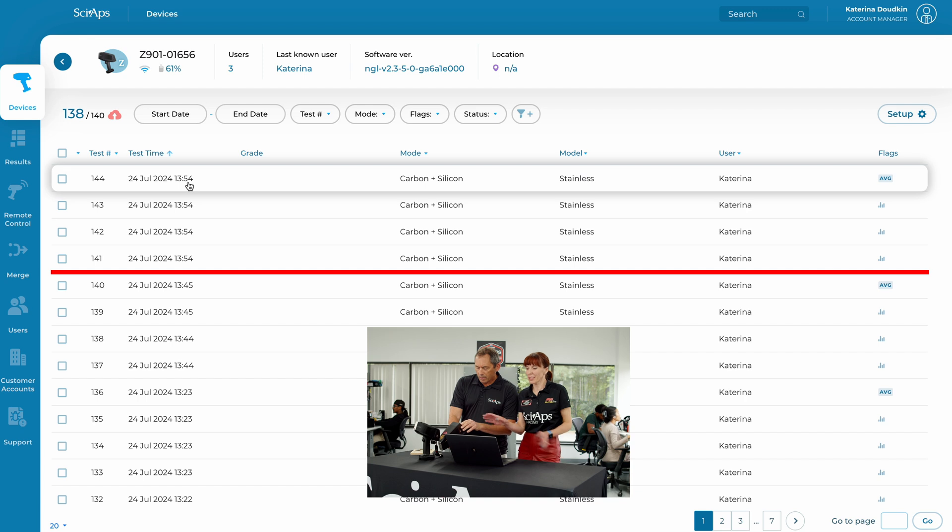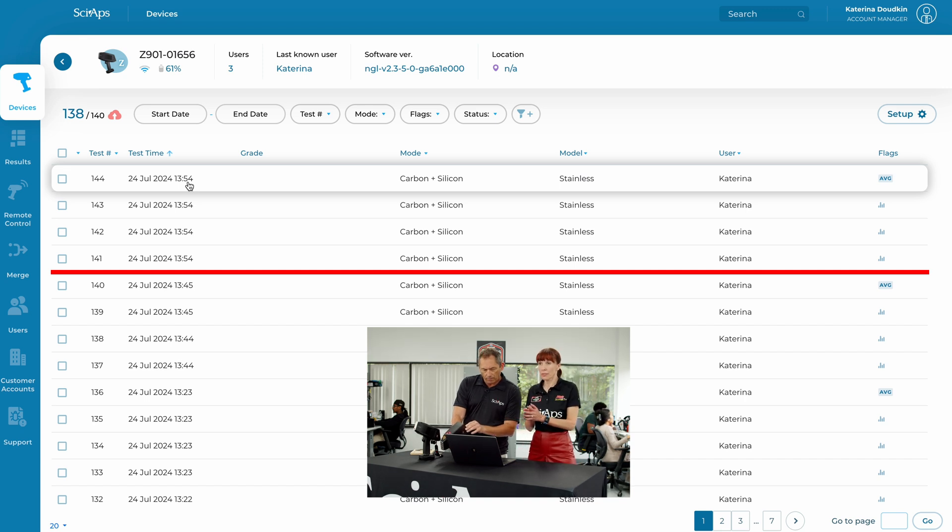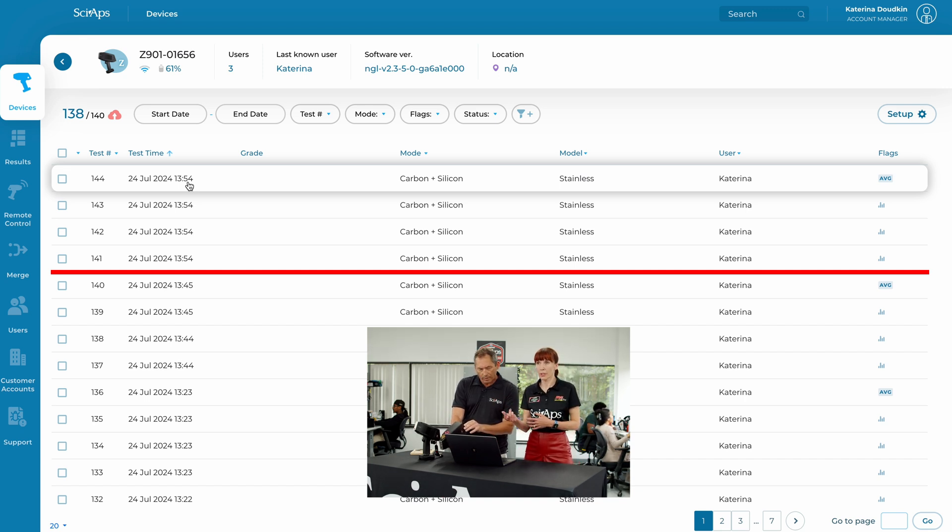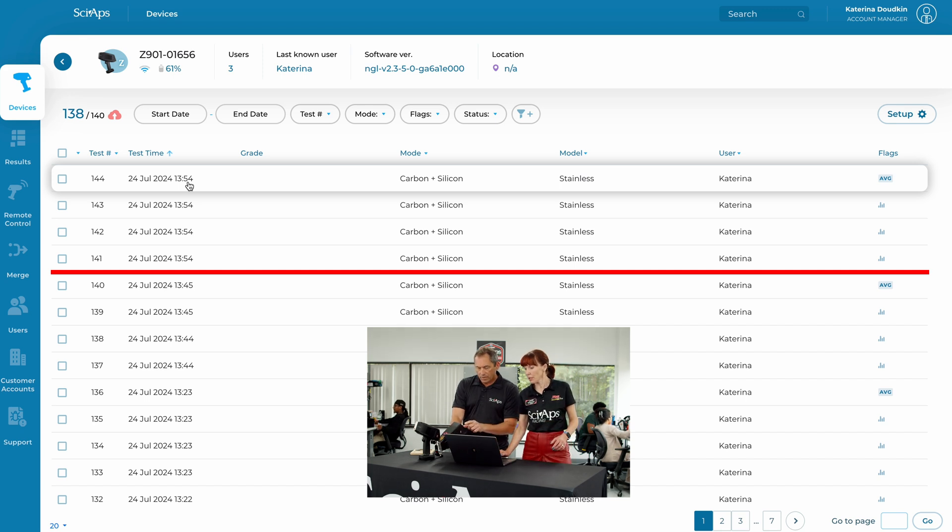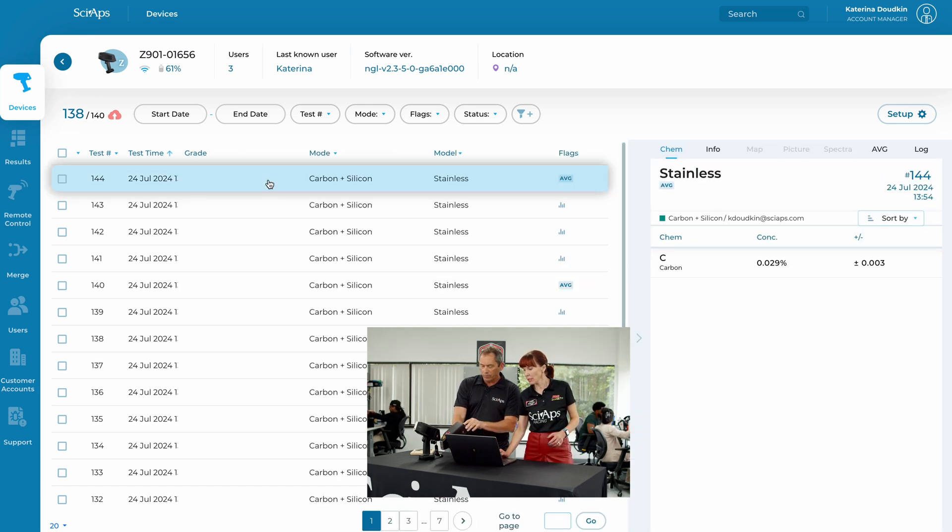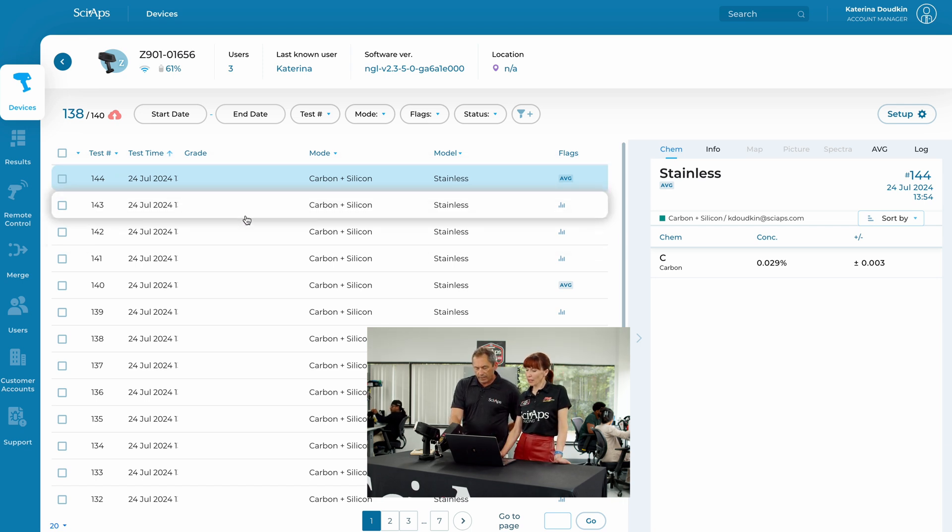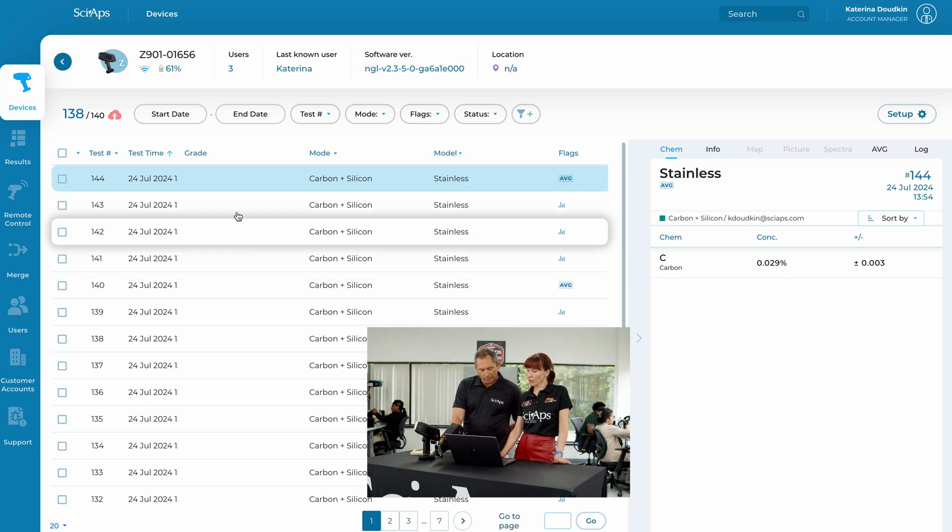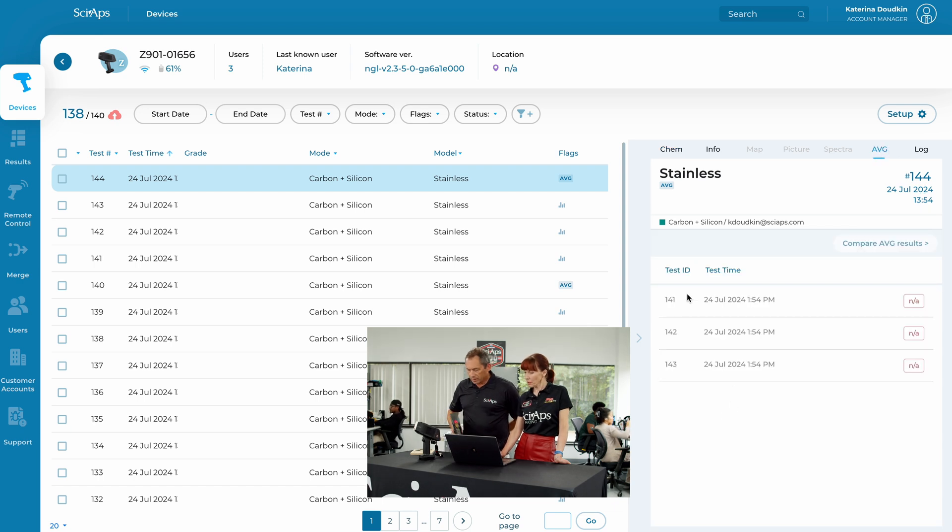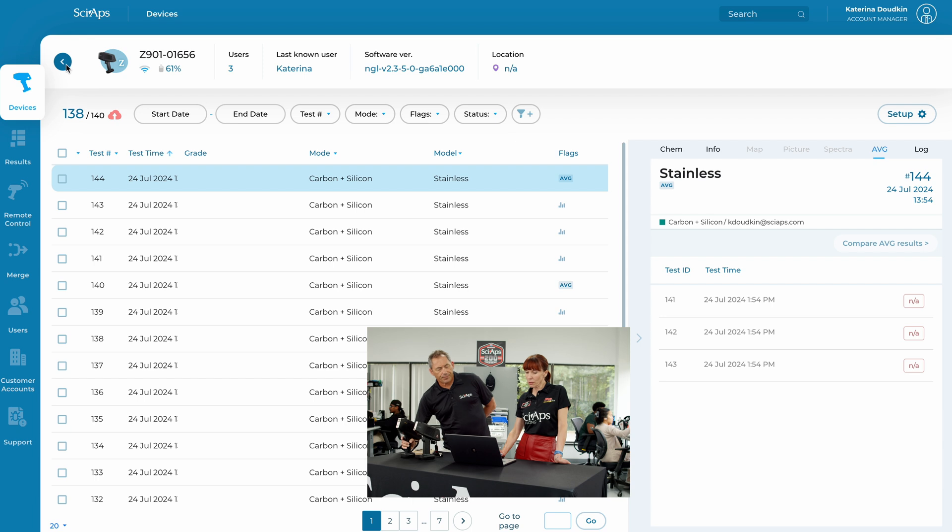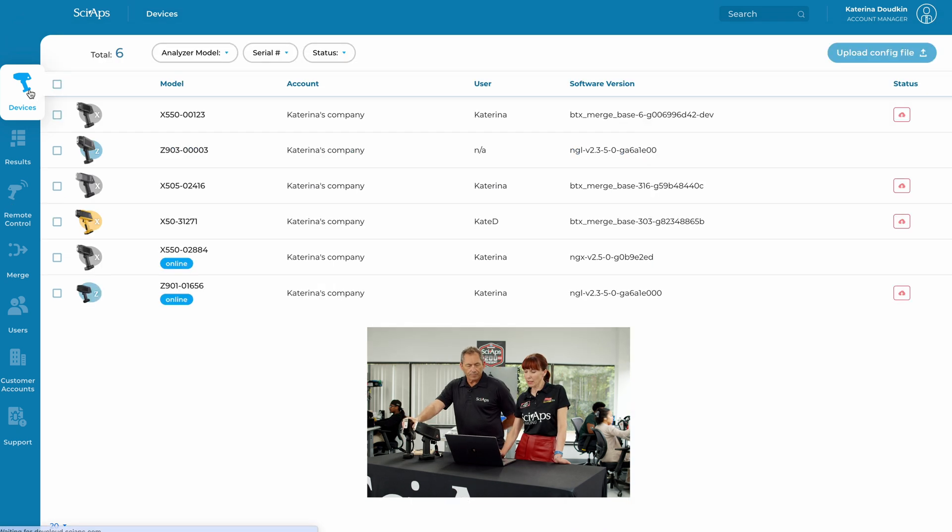I just want to remind that this mode is we upload results included into averaging, and at the end of the carbon sequence, we calculate average results. So you could see that this one is average results. So you can click on it. 0.029% plus 0.003. There you go. Very nice. And you also show results included into averaging calculation, and you could see here which ones were included. Individual tests. So it's pretty cool, right? It is.